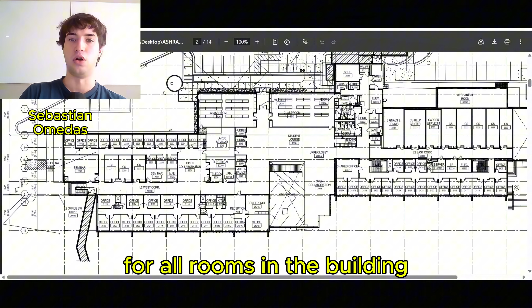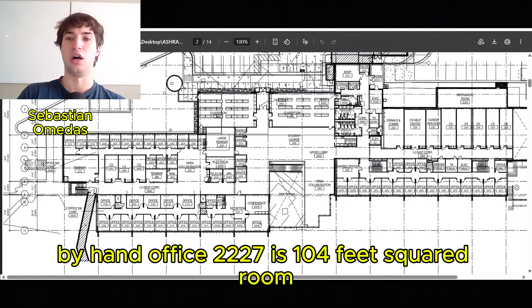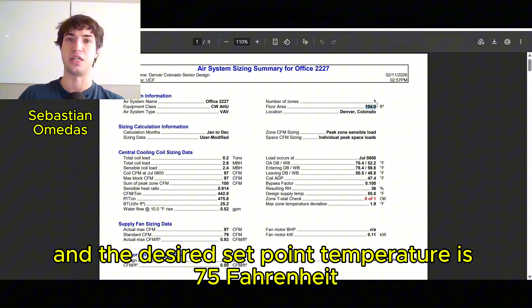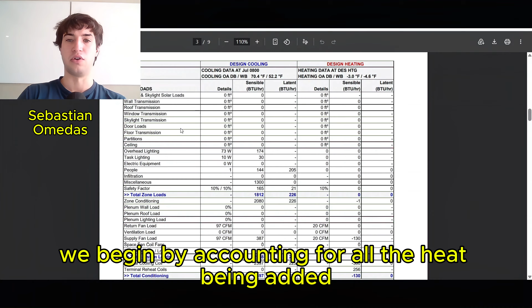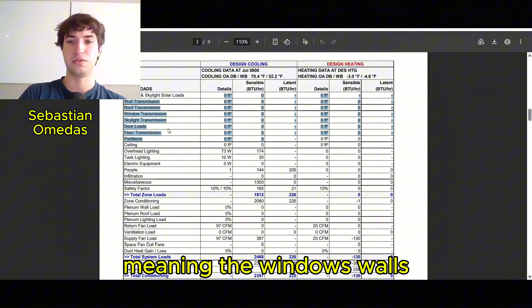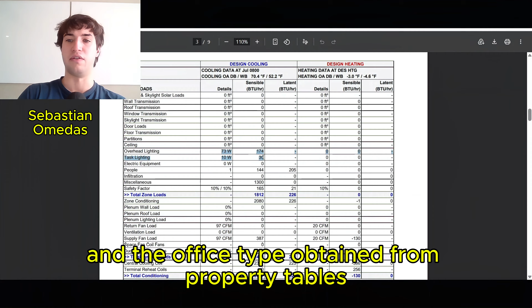To understand the calculations completed by HAP to obtain the desired energy calculations for all rooms in the building, the team has decided to perform a mathematical modeling of one room individually by hand. Office 2227 is a 104 square foot room, and the desired set point temperature is 75 Fahrenheit. All calculations will be compared with the HAP output report. We begin by accounting for all the heat being added inside the office. Here, the envelope is not exposed to the surroundings, meaning the windows, walls, roof, and door are not adding heat into the office. Next, the lighting loads depend on the area and the office type obtained from property tables.